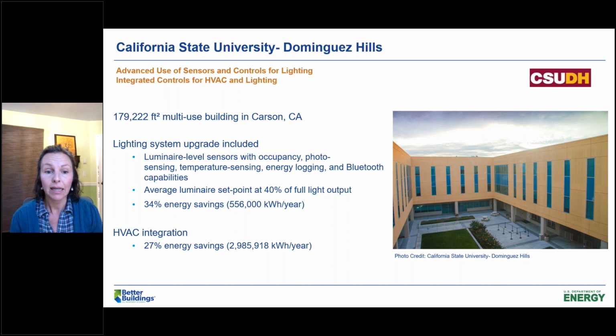The upgrade to LEDs included luminaire level sensors with occupancy, photo sensing, temperature sensing, energy logging, and Bluetooth capabilities, and they set the lights per the user's preferences. Then the occupants preferred, on average, 40% of the full light output, which helped yield a 34% energy savings. That network of sensors within the lighting system was also integrated with the building management system via BACnet, allowing them to set back for temperature control, yielding a 27% energy reduction to the HVAC system.